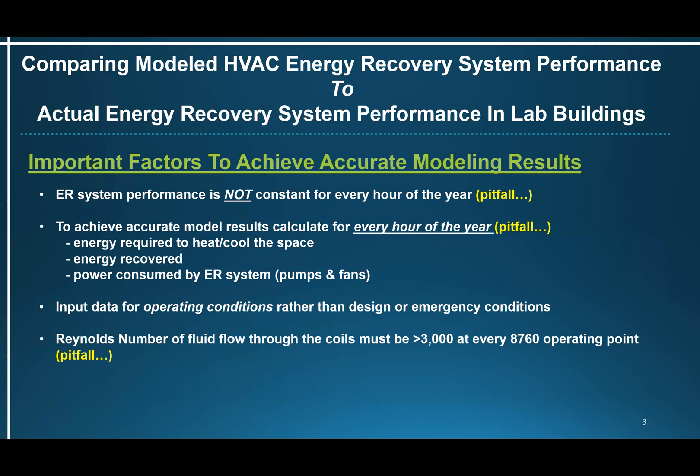And the Reynolds number. The Reynolds number of the fluid in the tubes of the energy recovery coils needs to be greater than 3000 to maintain turbulent flow. If it falls below 3000, the flow becomes partially laminar or even completely laminar, which destroys the heat transfer coefficient. Then the recovery performance of the system drops dramatically, even to the point where no energy is being recovered. So it's very important to ensure that the Reynolds number is calculated for every hour of the year and that it's always above 3000.